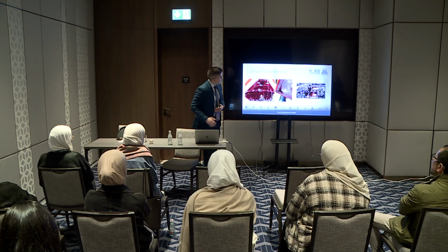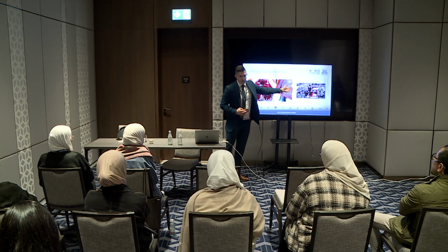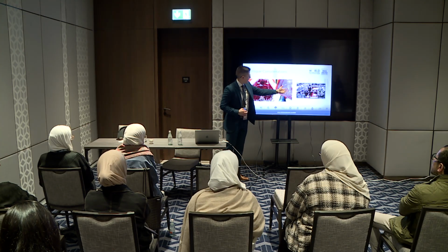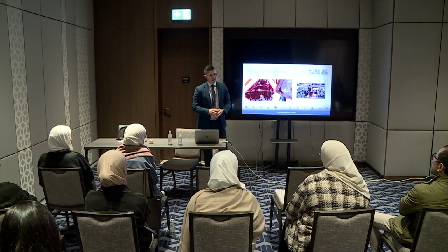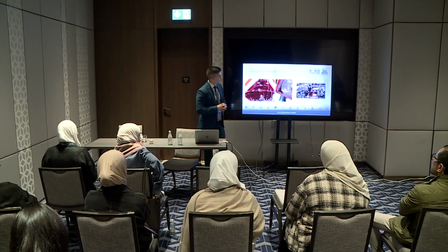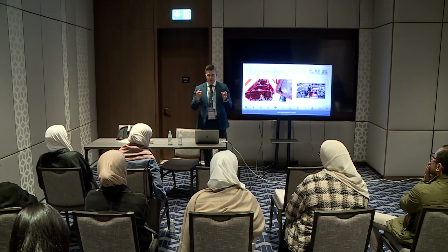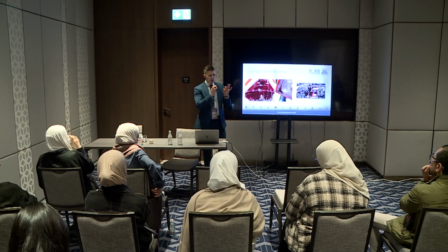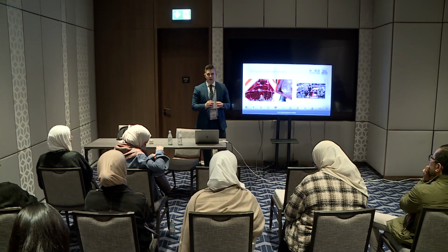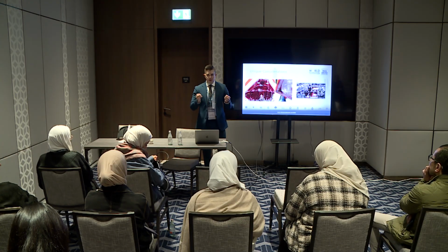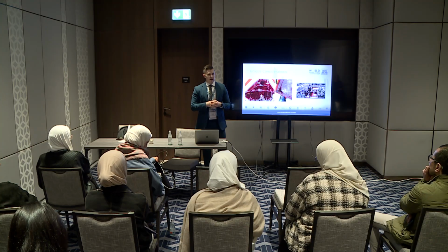of it. You can see here, this is from a pediatric case we had. The pediatric ECMO can be very complicated. We do some ECMO for congenital disease, and so the circuit configuration is even more complex. And you can see all the different connectors, and all of these spots are very prime location for fibrin deposition and thrombus growth.